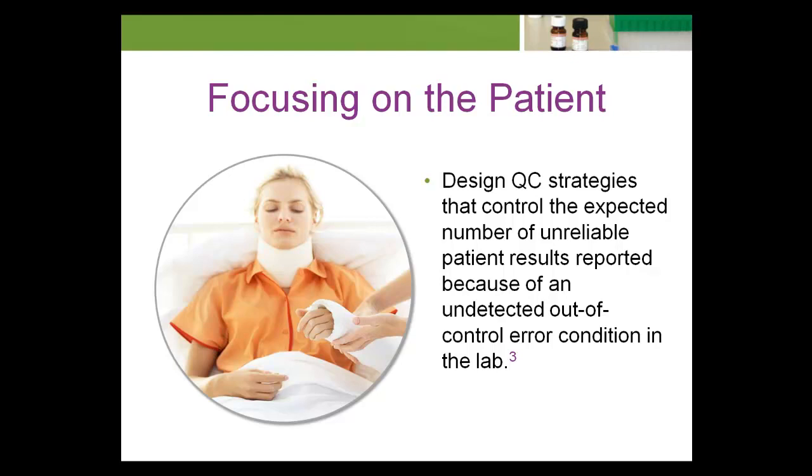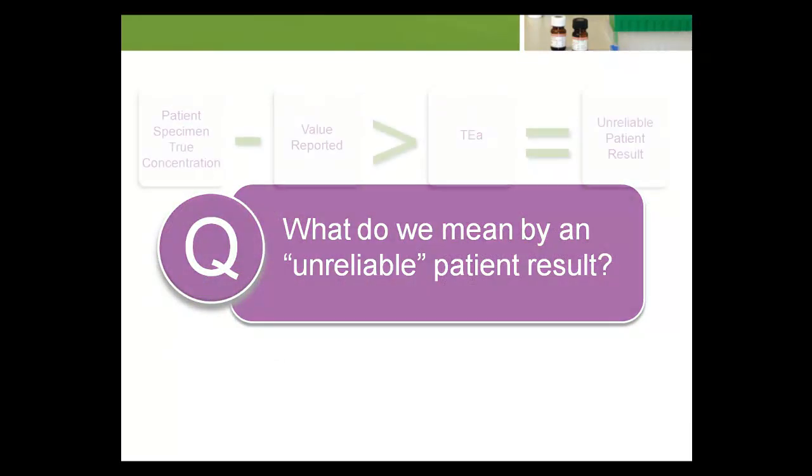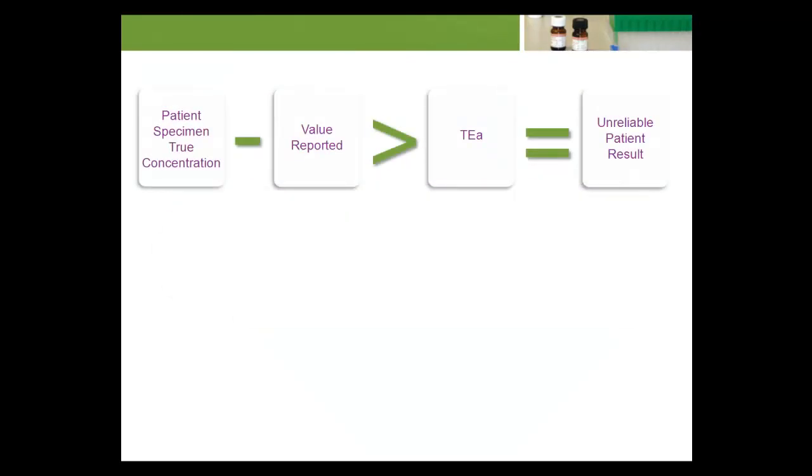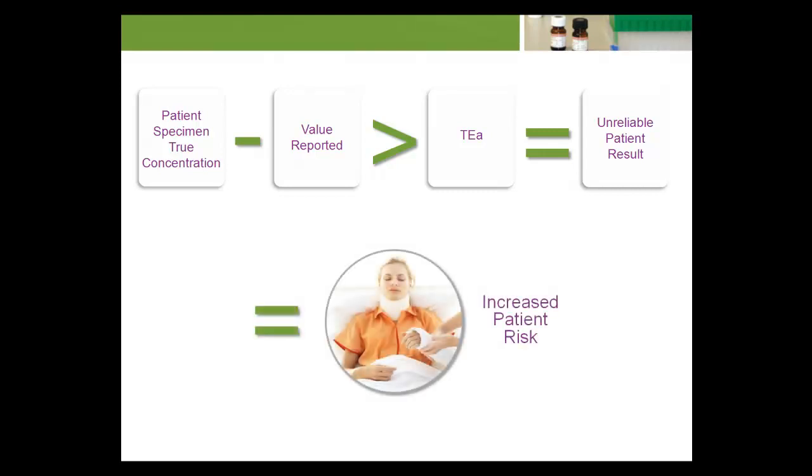What do we mean by an unreliable patient result? The quality of a patient result depends on the difference between the patient specimen's true concentration and the value reported by the laboratory. We define an unreliable patient result as one where the difference between the patient specimen's true concentration and the value reported exceeds a specified total allowable error, TEA. If the error in a patient's result exceeds TEA, we assume it places the patient at increased risk of experiencing a medically inappropriate action.